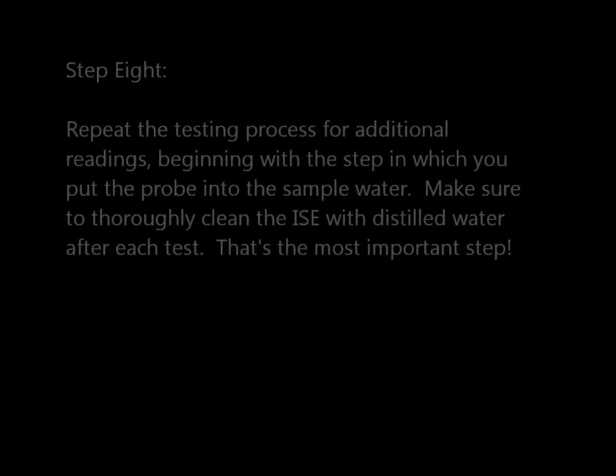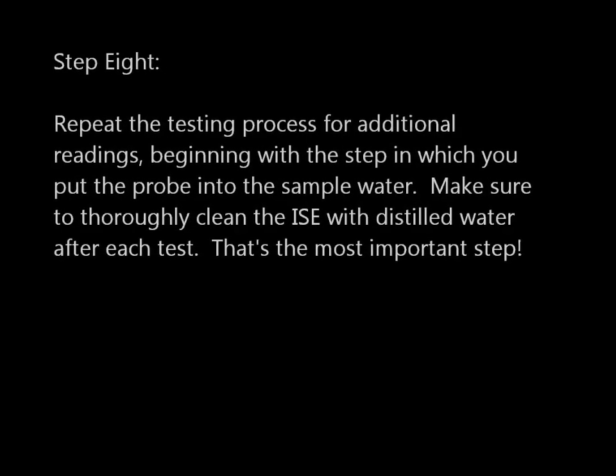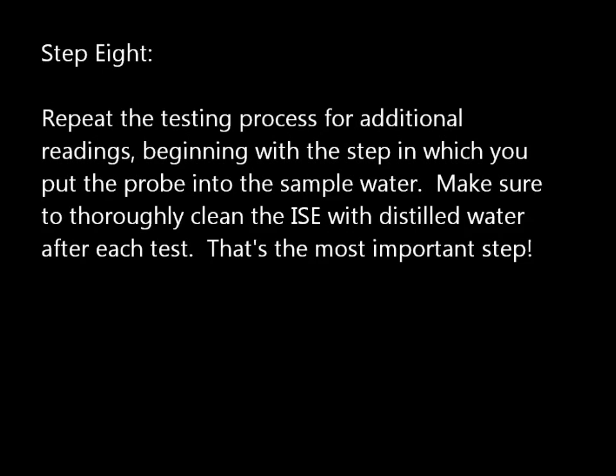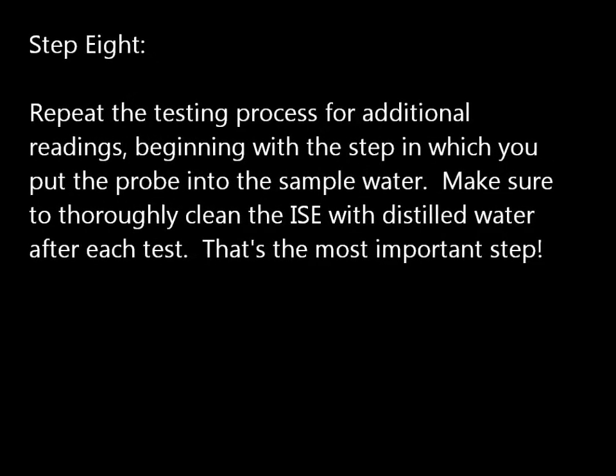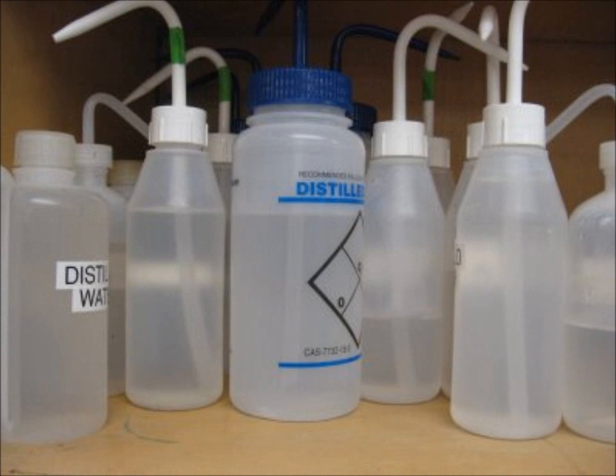Step 8. Repeat the testing process for additional readings, beginning with the step in which you put the probe into the sample water. Make sure to thoroughly clean the ISE with distilled water after each test. That's the most important step.